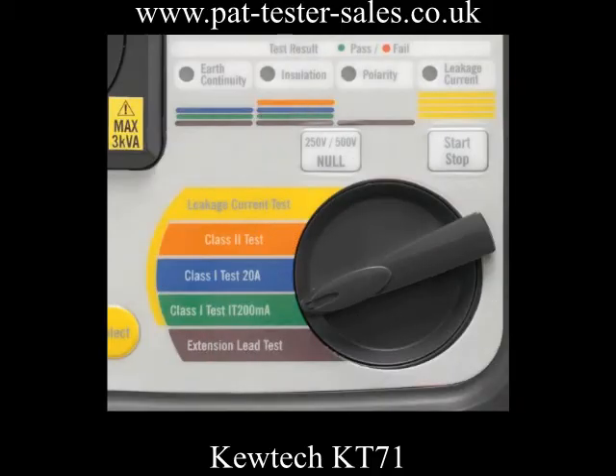It has five main options: the leakage current test, the class 2 test, class 1 test at 20 amps, class 1 test at 200 milliamps, and extension lead tests.